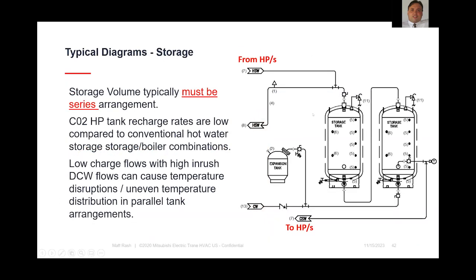So again, taking this further, when we start looking at the tank installation, you've got that hot water supply from the secondary side of the heat exchanger that's coming into that hot tank. You'll see a sparge fitting in those tanks up high at the hot connection. You also see a sparge fitting down low at the bottom connection. So you'll bring the hot water into the hot tank, out of the bottom of the hot tank, and then into any subsequent tanks. Again, the last one being the cold tank. And then we'll be drawing cold water typically out of the side of that cold tank down low back to the heat pump separation heat exchanger. This says from heat pumps, but this really should be to that separation heat exchanger. And then the cold water would come in typically through a separate connection at the bottommost position of that cold tank through that sparge fitting.